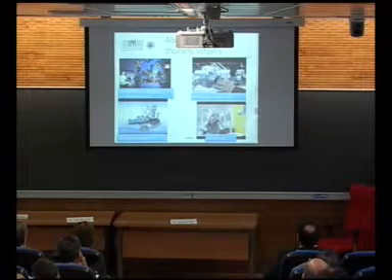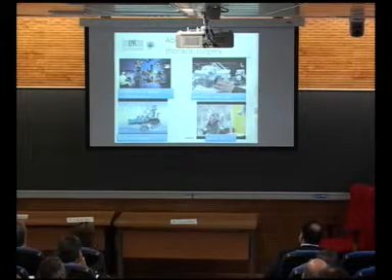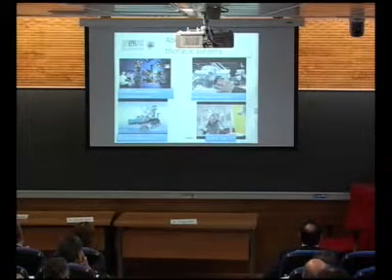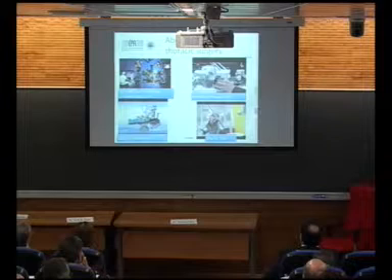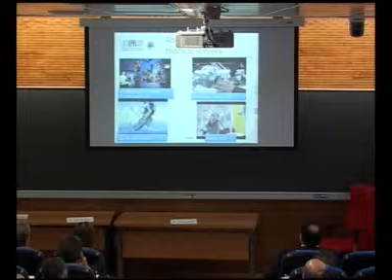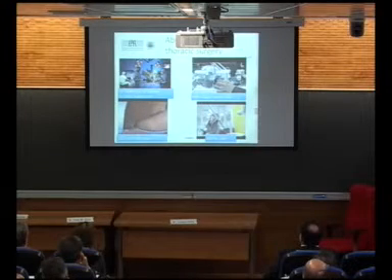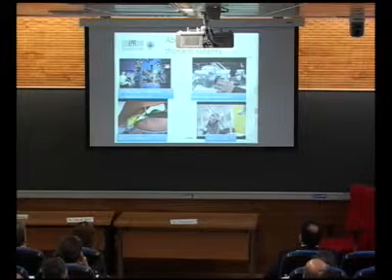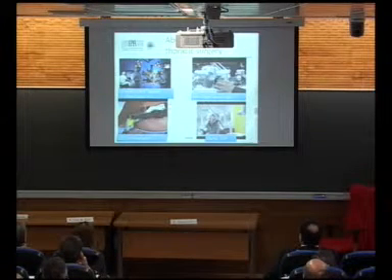As it is too big, normally it has an operating room that can be used only for that because it takes a lot of space. And in one of the hospitals in Lausanne, they had to reinforce the floor to use this robot in the hospital. So the trend now is to go towards more compact robots, as we can see. Also from the same company, they are now developing the single incision laparoscopic solution, which is this one where all the laparoscopes are using the same trocar. But basically, the robot is still the same, so it still has the drawback that it is very bulky. So this is a cholecystectomy. They are basically simulating the removal of the gallbladder.